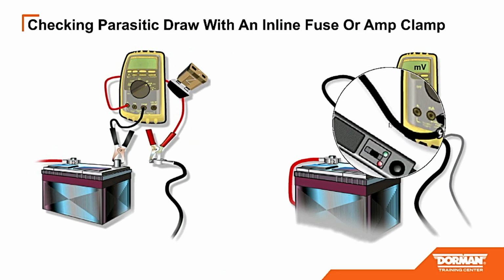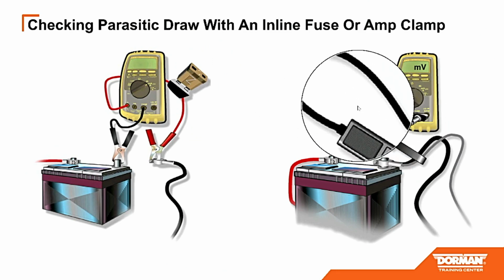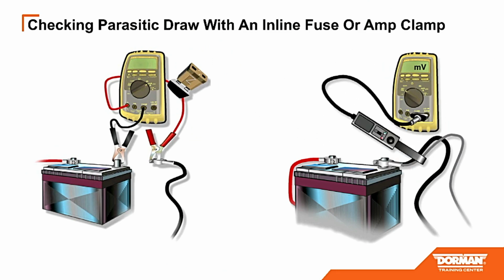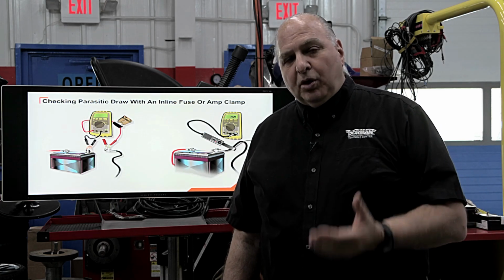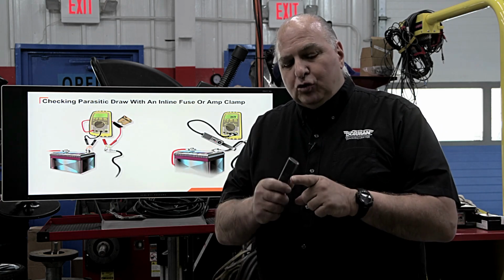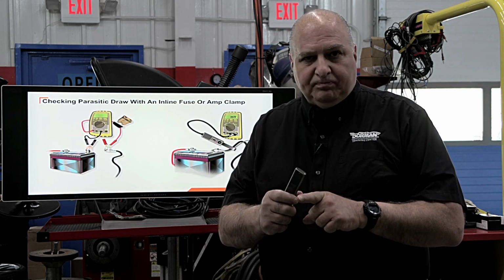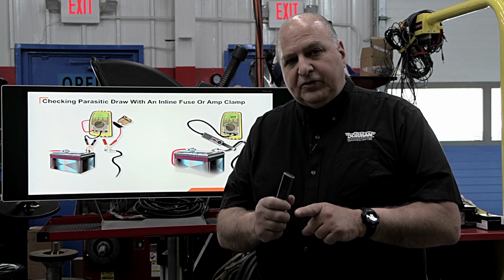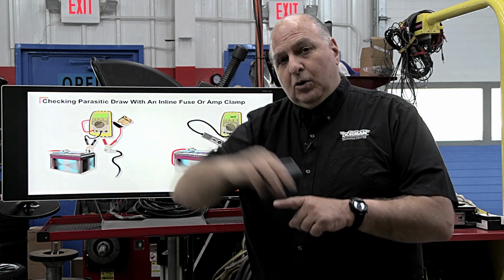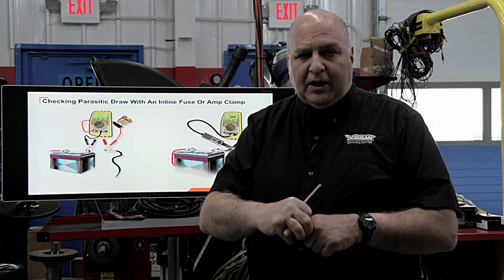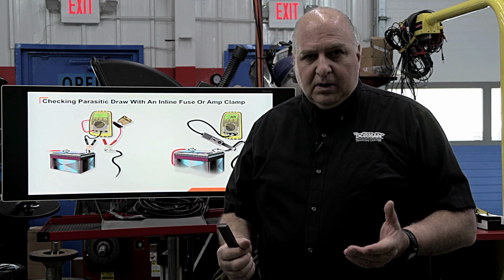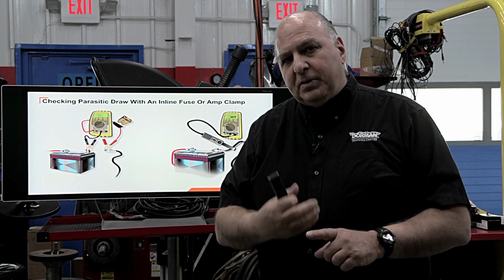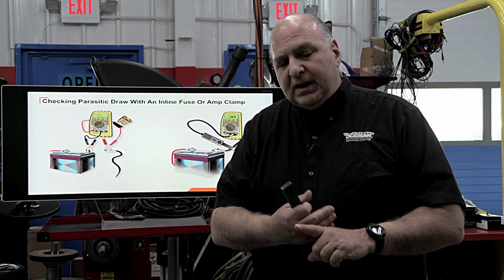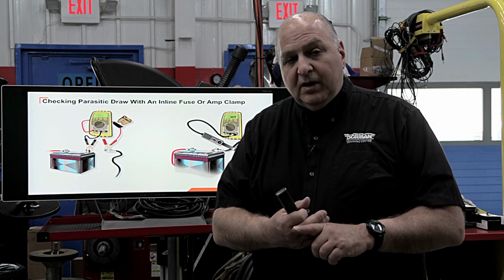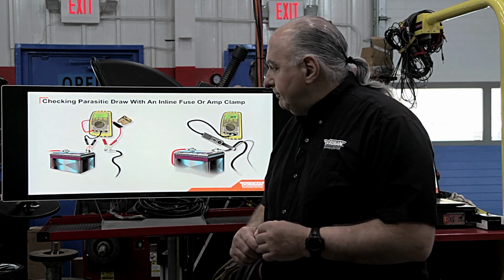The amp clamp is real good, but let's talk about it for a second. A few things with an amp clamp: you need to put it close to the wire first to zero it. If you don't zero it there, and instead zero it out away from the wire, you'll get the wrong reading. For the most accurate results, you want to be near the wire for the magnetic field, zero it there, then put it around the wires.